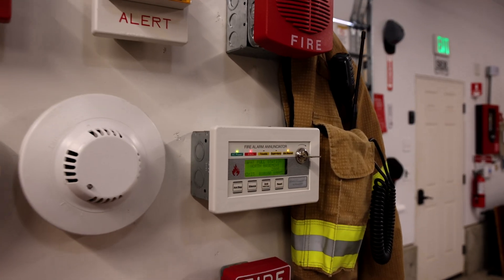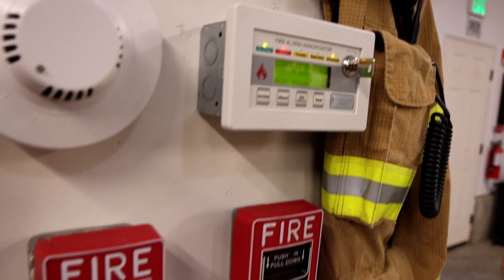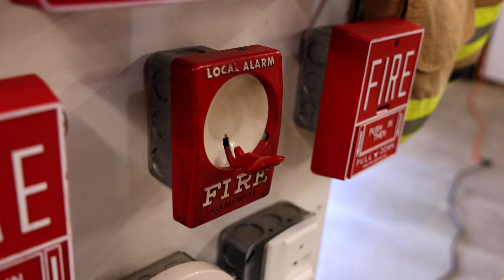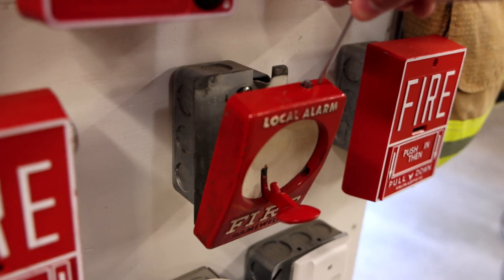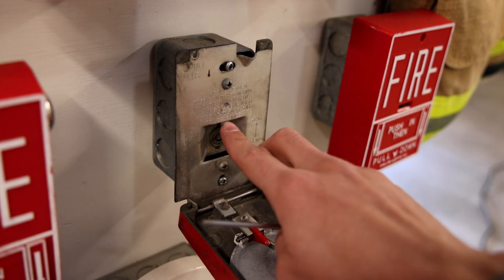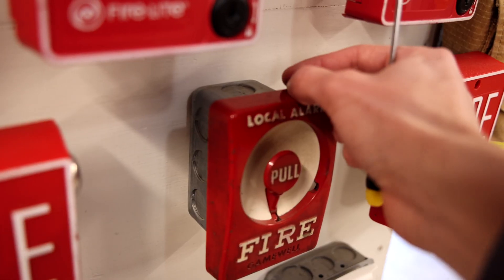Alright, I've gone ahead and silenced the system with the Fire-Lite annunciator here. And let's go ahead and reset the Gamewell Sentry. So with this model there is just a screw on the top here, and all you have to do is unscrew it — it's just a flat head. And then the whole front kind of comes down. Flip the switch, reset the handle, and then close the pull station and re-tighten the screw.